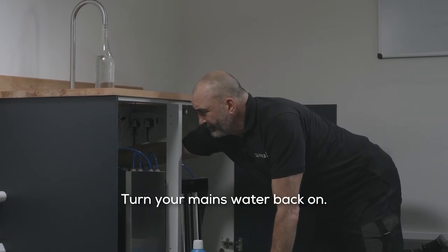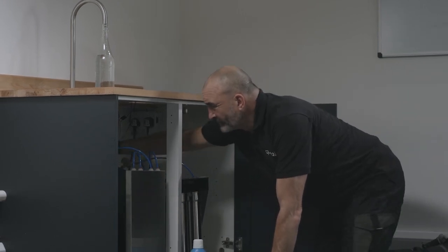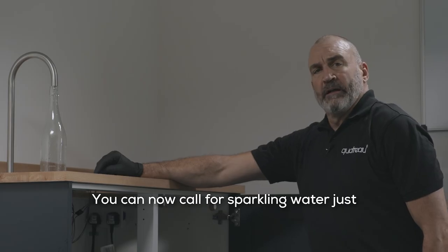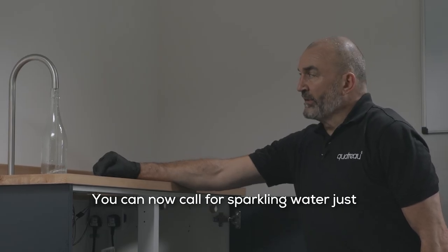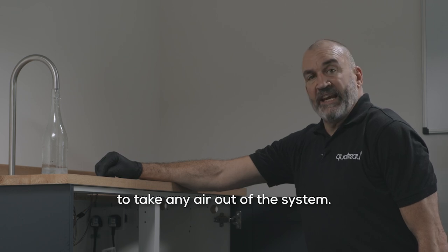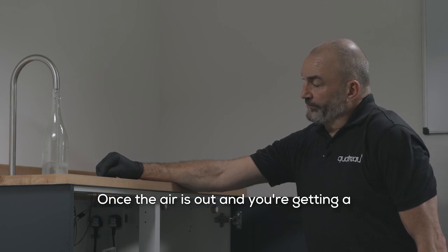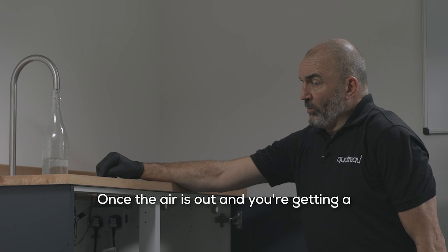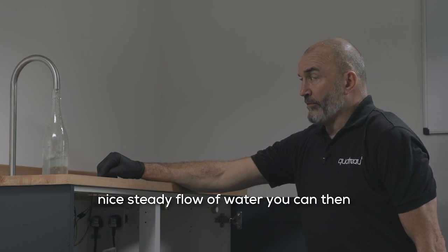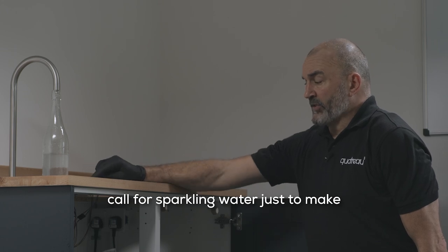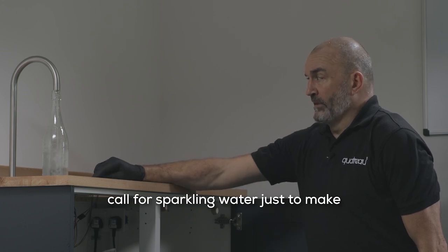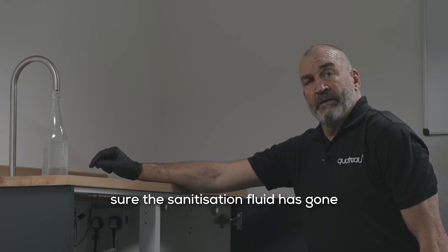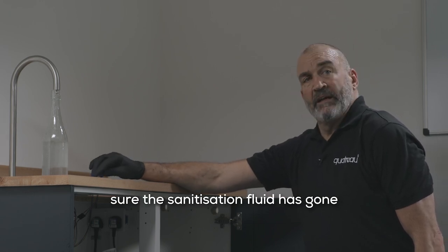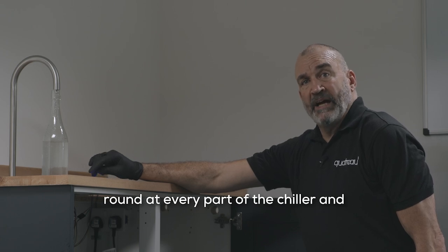Turn your mains water back on. You can now call for sparkling water just to take any air out of the system. Once the air's out and you're getting a nice steady flow of water, you can then call for sparkling water just to make sure the sanitisation fluid has gone round to every part of the chiller and the water control unit.